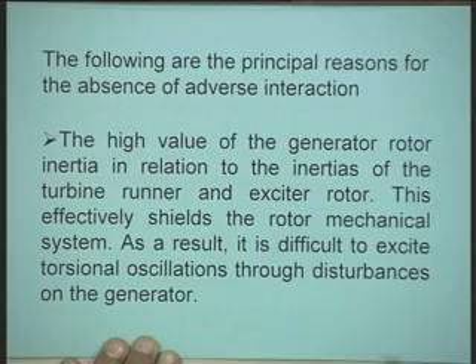Now, there are two principal reasons for no adverse interaction. One is the high value of generator rotor inertia in relation to the inertias of the turbine runner and exciter rotor. This effectively shields the rotor mechanical system. As a result, it is difficult to excite torsional oscillations through disturbances on the generator. That is, whenever some disturbance takes place in the generator, these oscillations are not excited. The other is that the runner is moving in water, and therefore there exists good viscous water wheel damping. This makes the inherent damping of the torsional oscillations for hydro units significantly higher than the steam turbine generators.